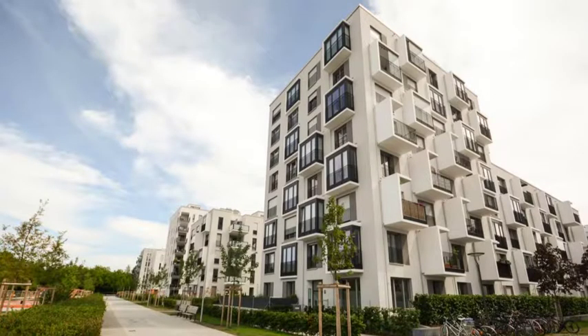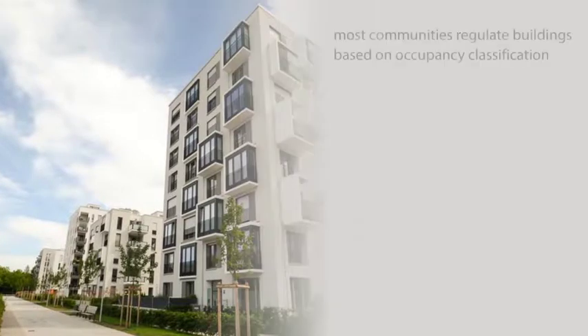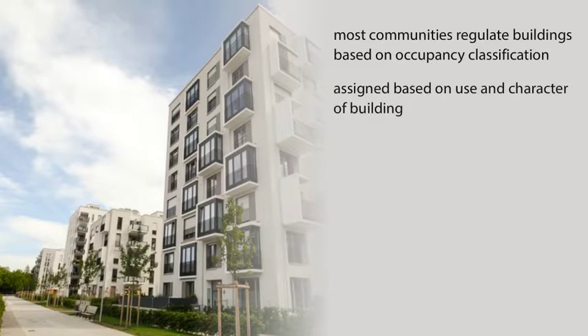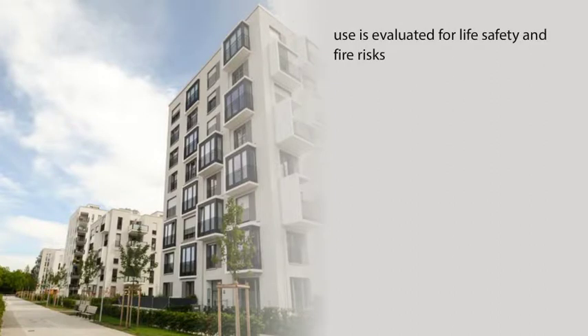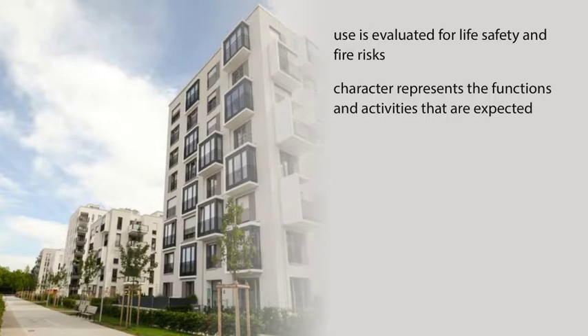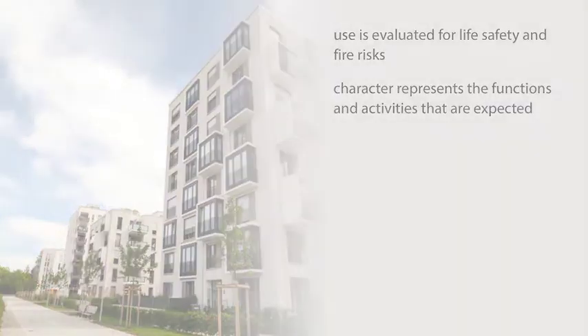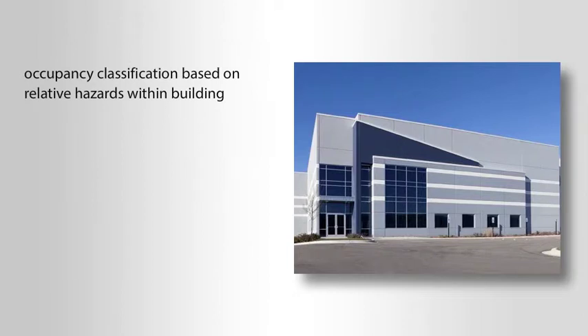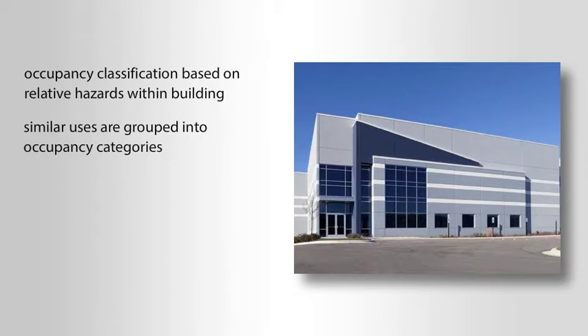Before you proceed into the course content, you must understand that most communities regulate their buildings based on the occupancy classification, which is assigned based on the use and character of a building. A building's use is evaluated for life safety and fire risks, and its character represents the functions and activities expected to occur in the building. An occupancy classification is based on the relative hazards within a building, and similar uses are grouped into occupancy categories.